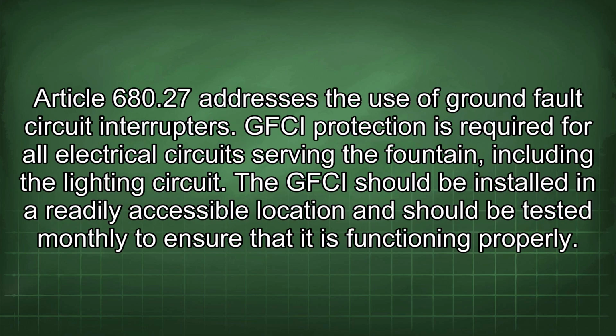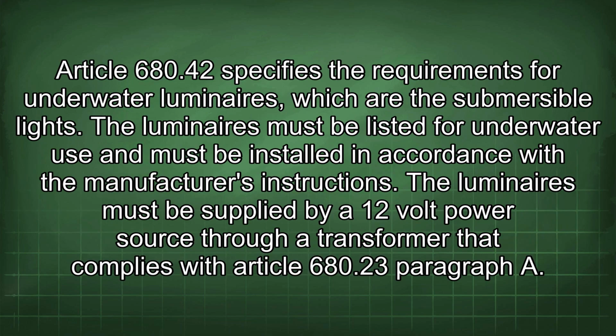Article 680.27 addresses the use of ground fault circuit interrupters. GFCI protection is required for all electrical circuits serving the fountain, including the lighting circuit. The GFCI should be installed in a readily accessible location and should be tested monthly to ensure that it is functioning properly. Article 680.42 specifies the requirements for underwater luminaires, which are the submersible lights.